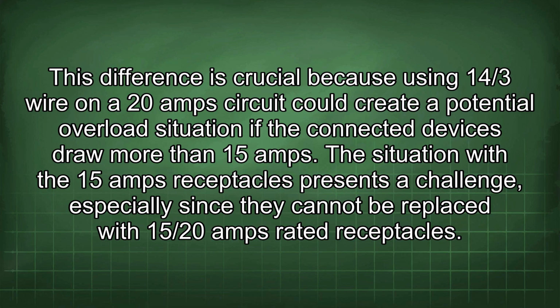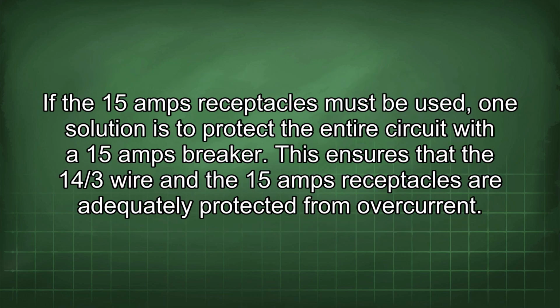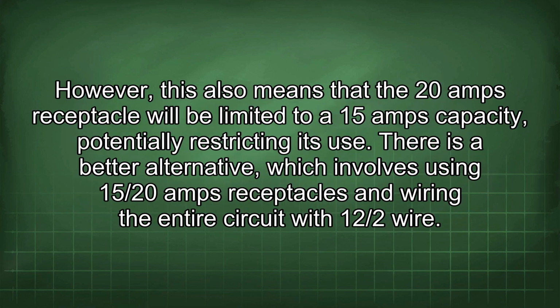The situation with the 15 amps receptacles presents a challenge, especially since they cannot be replaced with 15/20 amps rated receptacles. If the 15 amps receptacles must be used, one solution is to protect the entire circuit with a 15 amps breaker. This ensures that the 14/3 wire and the 15 amps receptacles are adequately protected from overcurrent. However, this also means that the 20 amps receptacle will be limited to 15 amps capacity, potentially restricting its use.